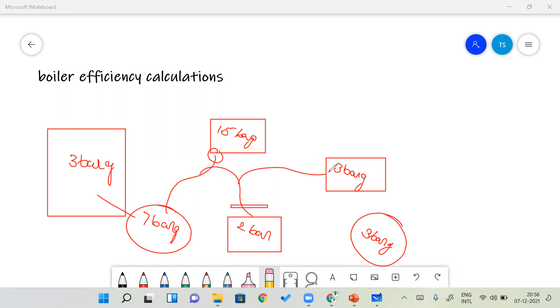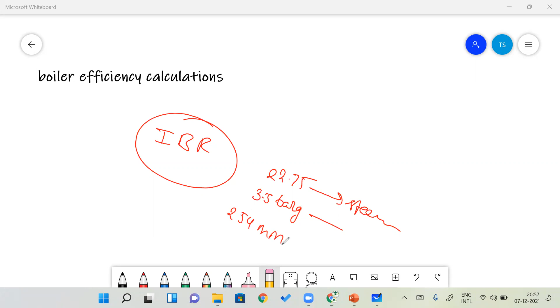Because there are disasters, some safety regulations are required. Those safety regulations are nothing but the IBR regulations. So just check what the IBR regulations are. It is like 22.75 liters. If there is any enclosure vessel which is greater than 22.75 liters and is producing steam, then it comes under IBR. Any pressure which is greater than 3.5 bar gauge also comes under IBR, or any steam piping which is more than 254 mm also comes under IBR regulations.